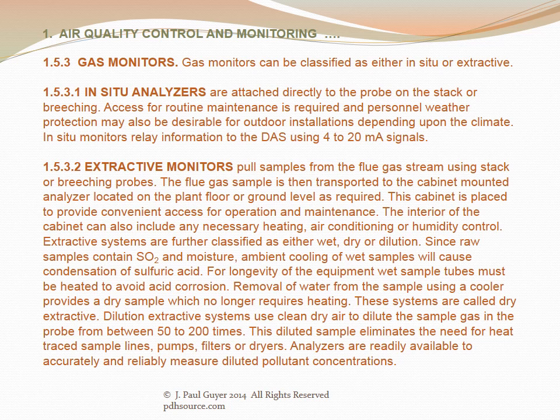Since raw samples contain SO2 and moisture, ambient cooling of wet samples will cause condensation of sulfuric acid. For longevity of the equipment, wet sample tubes must be heated to avoid acid corrosion. Removal of water from the sample using a cooler provides a dry sample which no longer requires heat — these systems are called dry extractive. Dilution extractive systems use clean dry air to dilute the sample gas in the probe by 50 to 200 times, eliminating the need for heat-traced sample lines, pumps, filters, or dryers. Analyzers are readily available to accurately measure diluted pollutant concentrations.